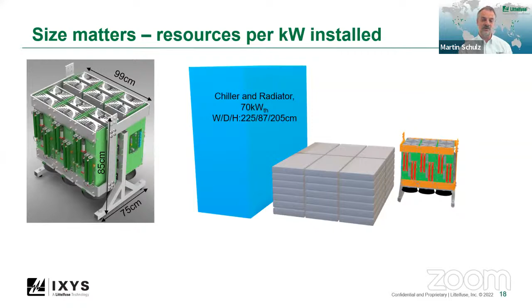And if you try paralleling those, you would need 42 units to fulfill the 2.2 megawatt solution. But you only need this one stack, consisting of two B6C topologies, and the efficiency is so high that you get away with forced air cooling.